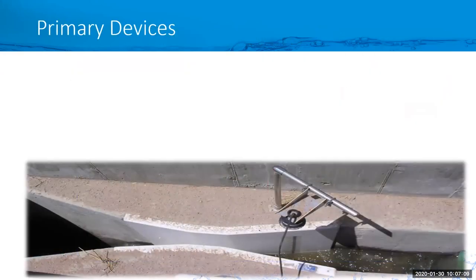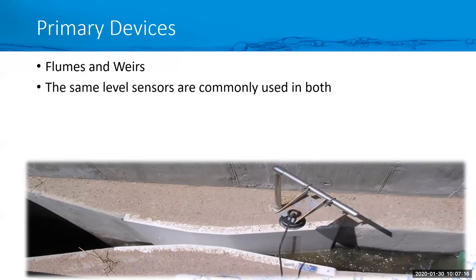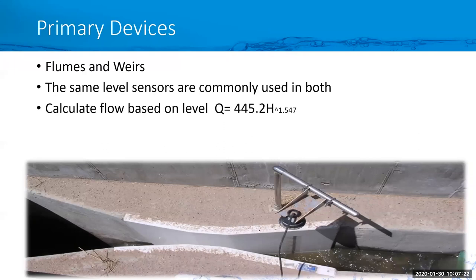So here's a look at a Parshall flume with an ultrasonic sensor. The primary devices are weirs and flumes. The same level sensor can be used with both, with a weir or a flume. So with a flume, the flow calculations are based on level. We take the level, we apply it to a formula depending on what size or type of flume you have, and that will give us a flow rate.